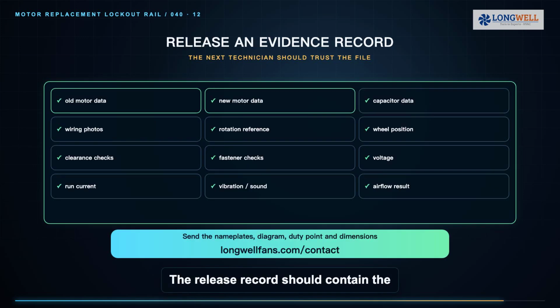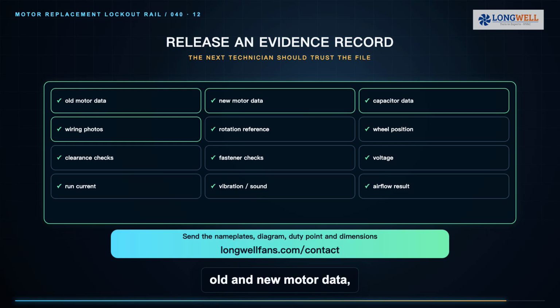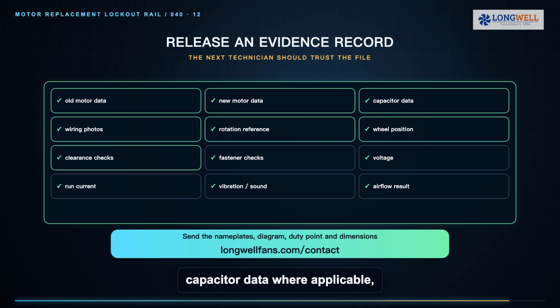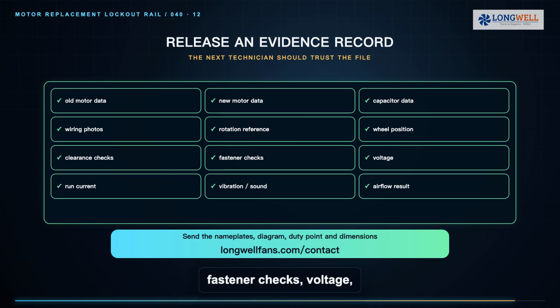The release record should contain the old and new motor data, capacitor data where applicable, wiring photos, rotation reference, wheel position, clearances, fastener checks, voltage, running current, vibration or sound observation, airflow result and the restored safety devices. That record turns a one-time repair into evidence the next technician can trust.